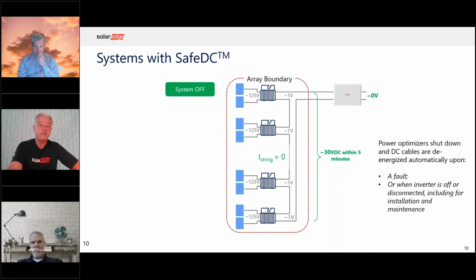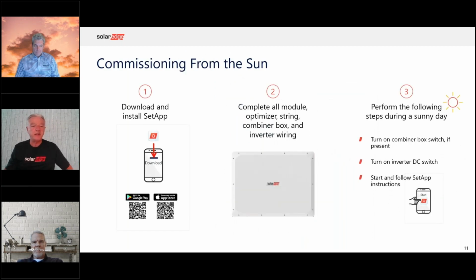And that happens within 5 minutes. So you shut down the inverter, or if there's some kind of an arc or a short circuit, or you lose grid power, or for some reason the inverter shuts down, then this safe DC mode turns on and all of the optimizers go down to 1 volt DC. So that's inherent in all of our SolarEdge inverters, is that safe DC, very safe architecture.